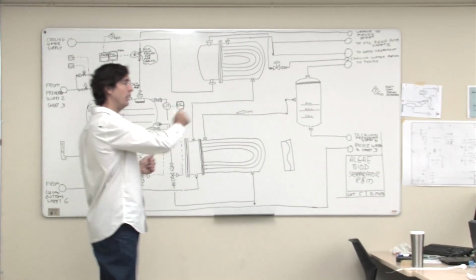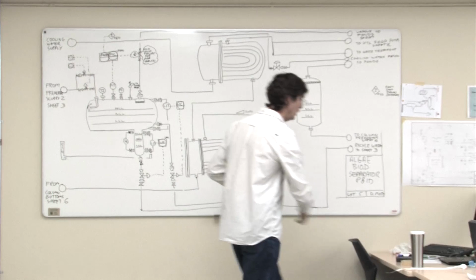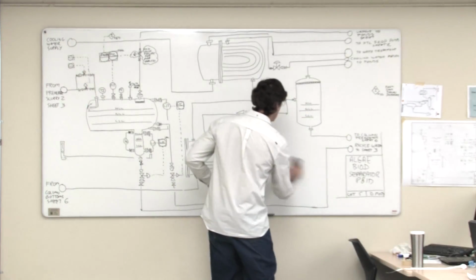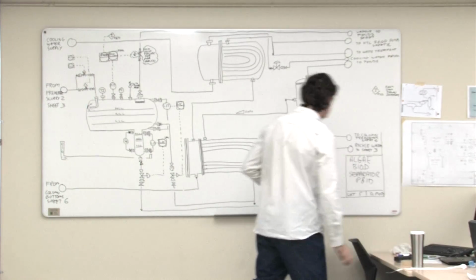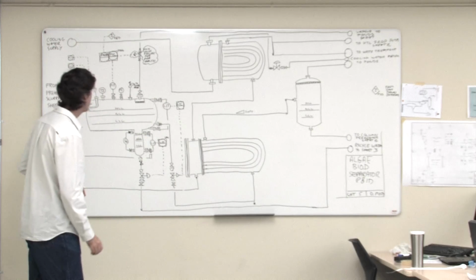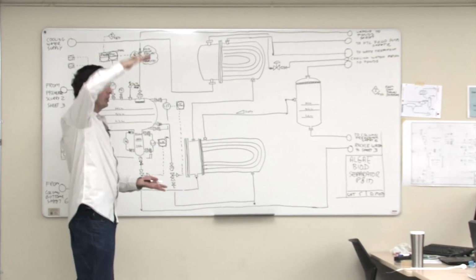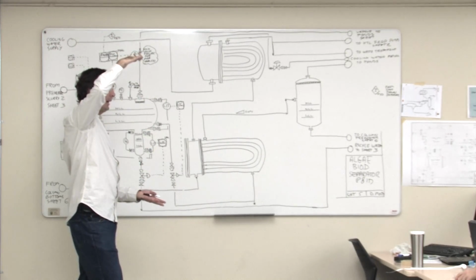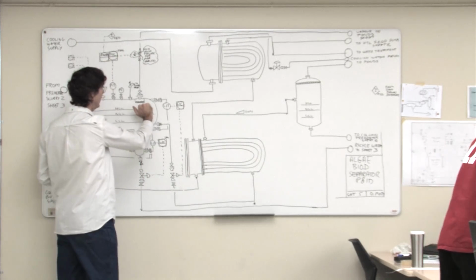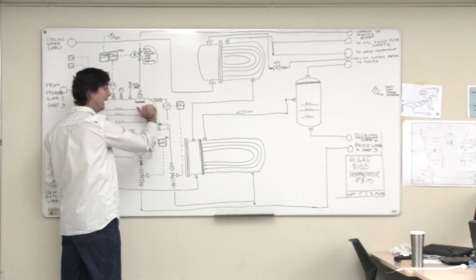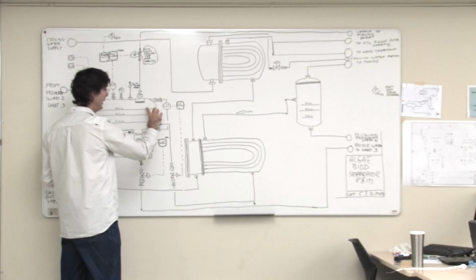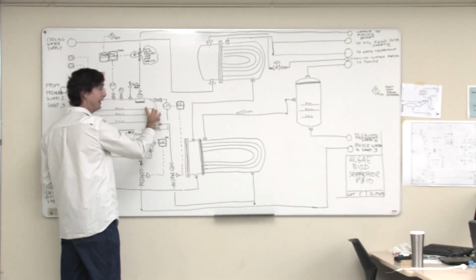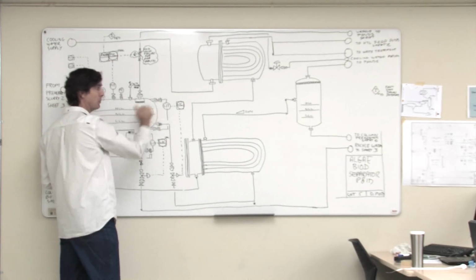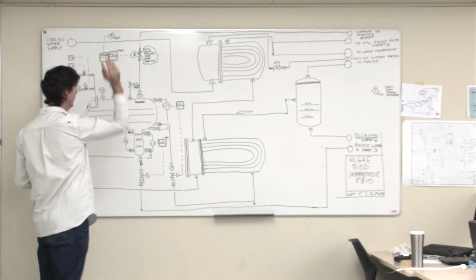Why is the level transmitter taking information above the high liquid level? The level transmitter is a differential device. It needs to measure the pressure above the liquid level, and the bottom leg of the level transmitter measures the pressure down there. So it should always be above where the maximum liquid level is, you want to get it well out of the liquid.